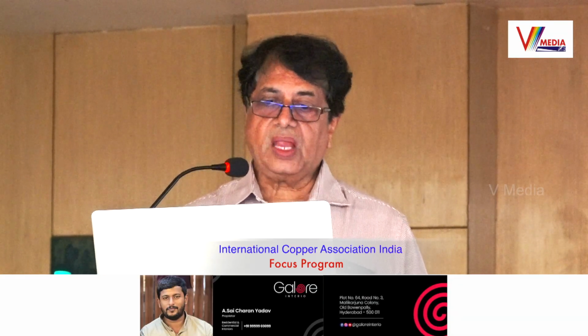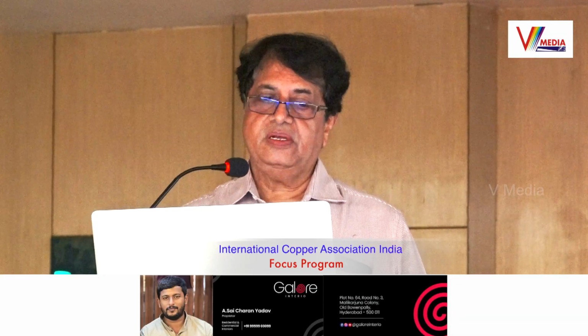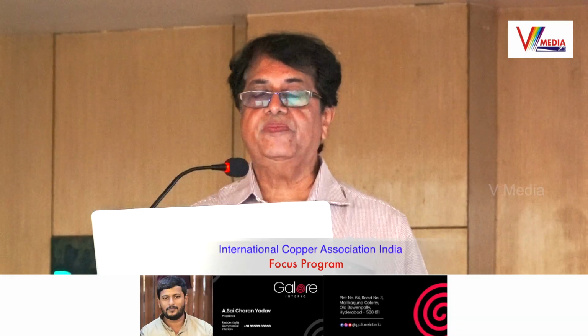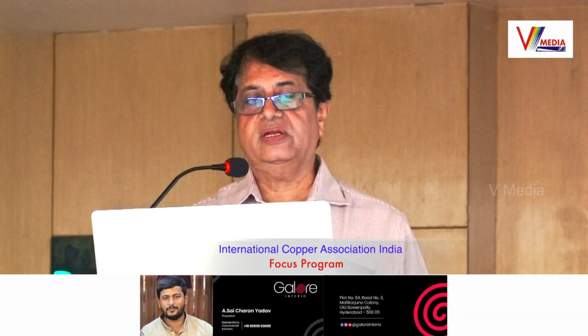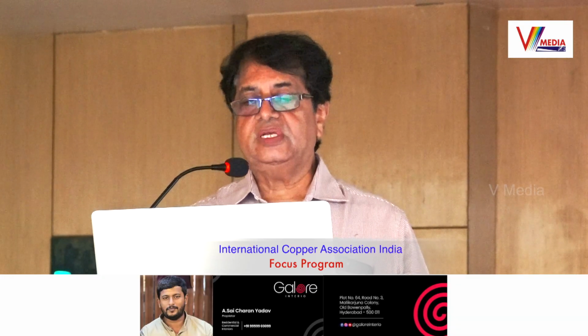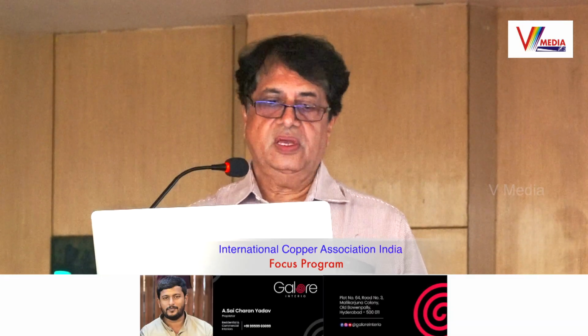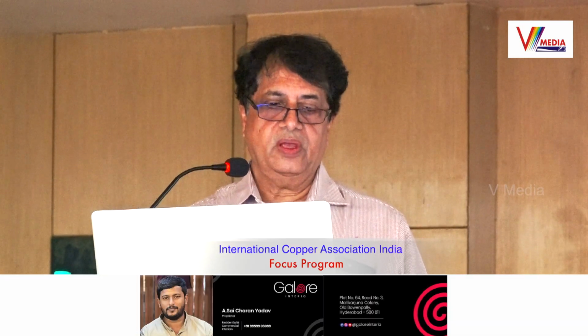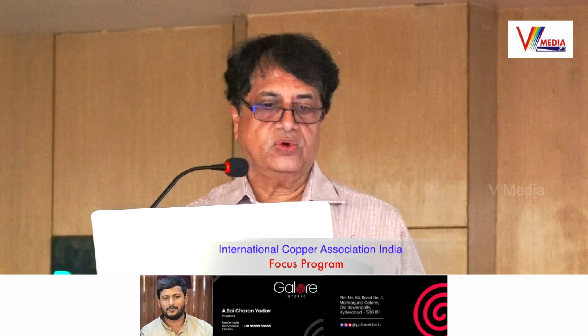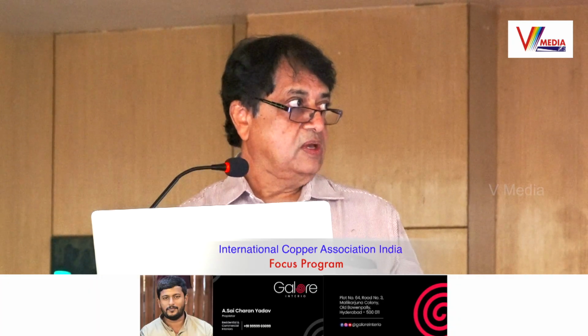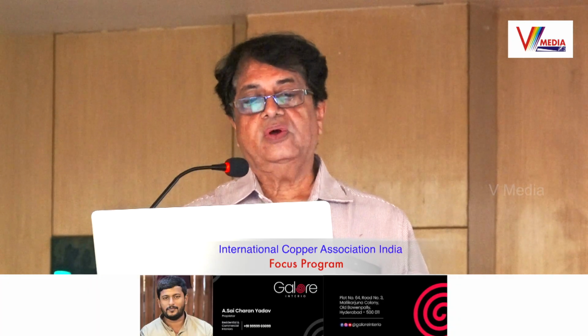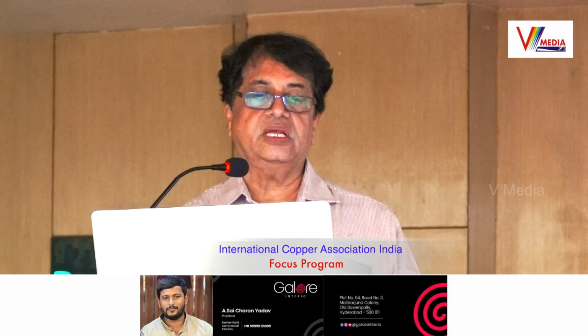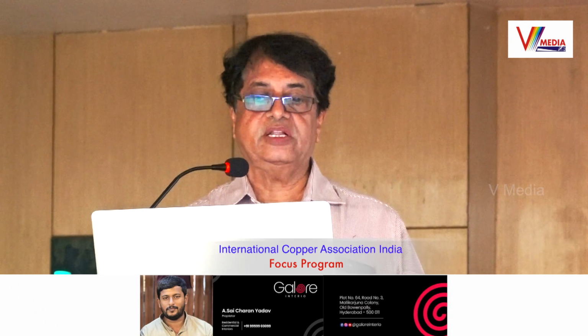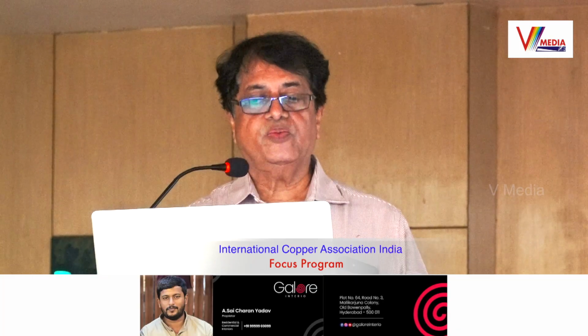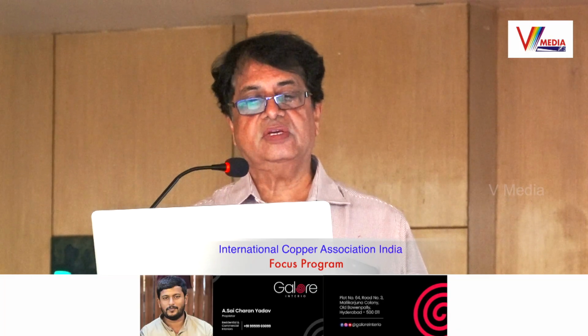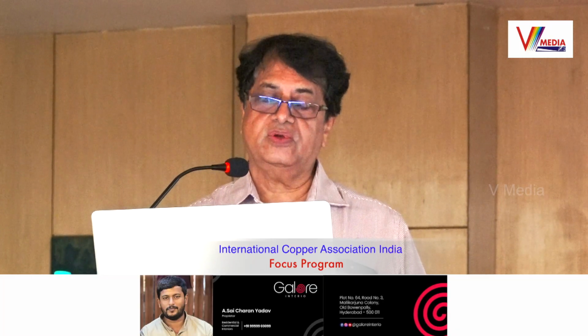and then the architect should make such arrangements in his drawings. One more requirement: you must know that independent electrical shafts are required in the building. If we don't maintain those independent electrical shafts, an accident may happen. Here, this is the actual photo which was taken from one of the buildings in Mumbai. The fire initiated on the 10th floor, and this picture was taken on the 20th floor. Why did this happen? There was no proper sealing at the floor level, and that's why the fire passed from the lower floor to the upper floor.